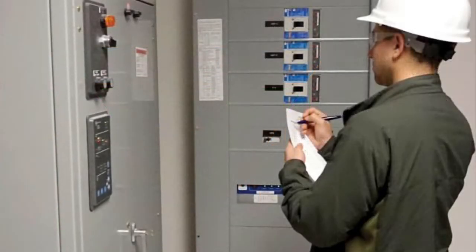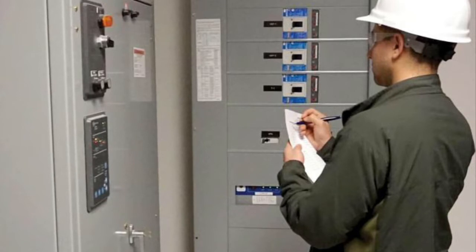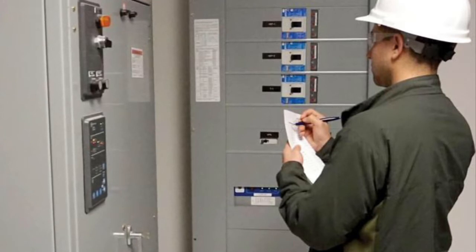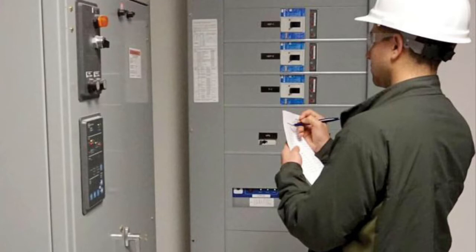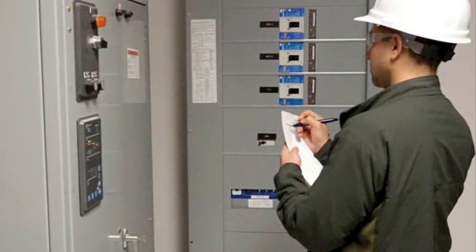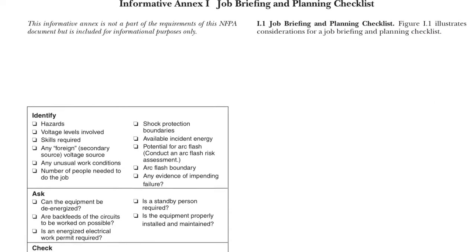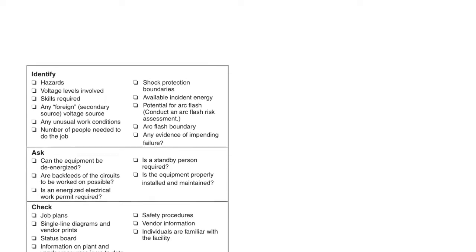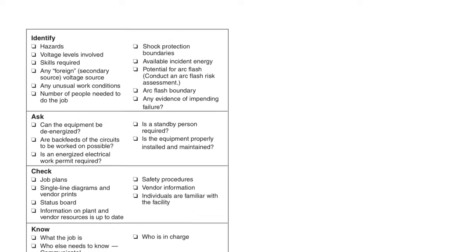Before starting each job that involves exposure to electrical hazards, the employee in charge shall complete a job safety plan and conduct a job briefing with the employees involved. The job safety plan shall be completed by a qualified person, be documented, include a description of the job and individual tasks, identification of electrical hazards associated with each task, and a shock risk assessment. The shock risk assessment must identify shock hazards, estimate the likelihood and severity of injury, and determine if additional protective measures including PPE are required. The job briefing shall cover the job safety plan and information on the energized electrical work permit if required. The job briefing and planning checklist is located in Informative Annex I of the NFPA 70E and in the safety reference job on Procore.